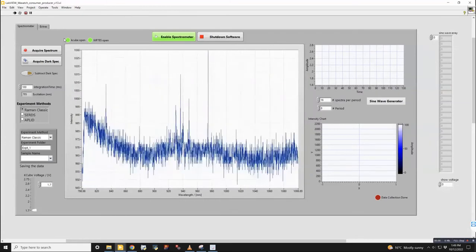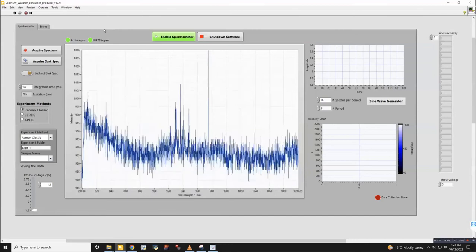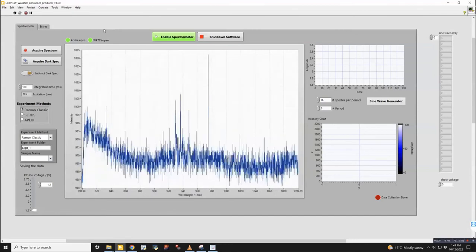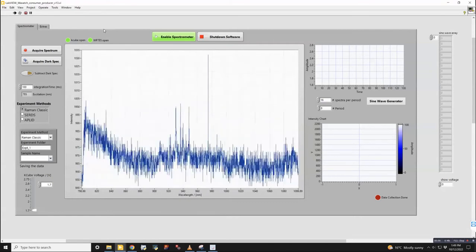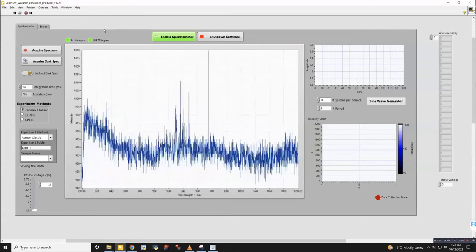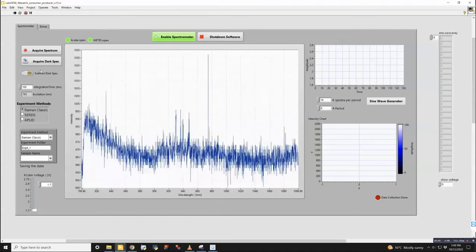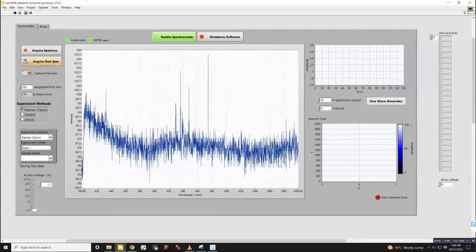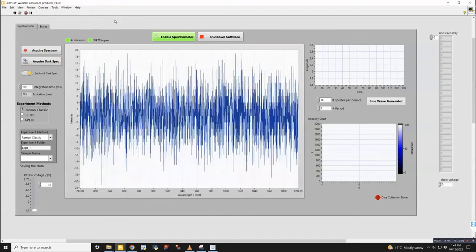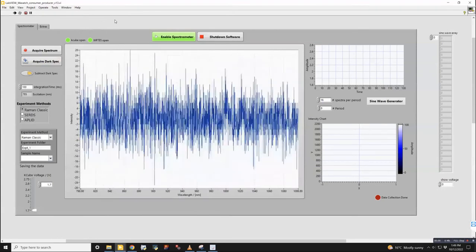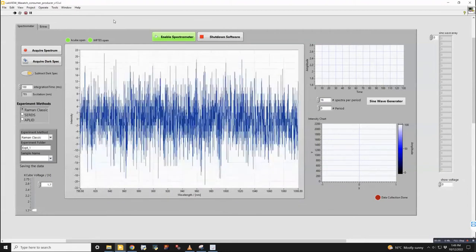Yeah, so I look for these green lights over here to make sure that I've successfully initialized the connection. Right now the laser's off, so this is the raw pattern that the detector is going to pick up in the absence of any light that it's collecting. In order to account for this, you can acquire a dark spectrum. This is saved in memory, and you can subtract it away so that all that remains is the noise on the detector. This is dependent on the exposure time.